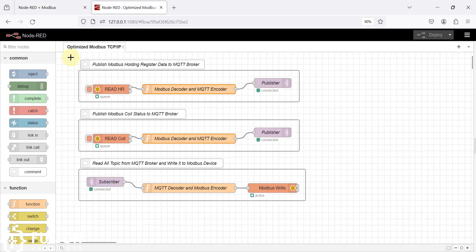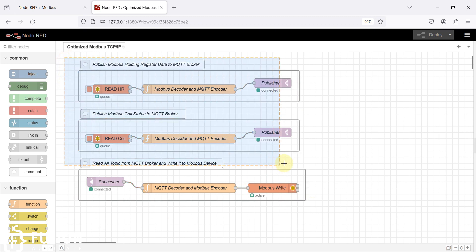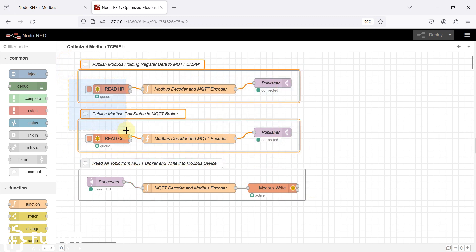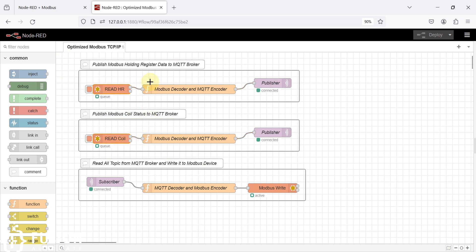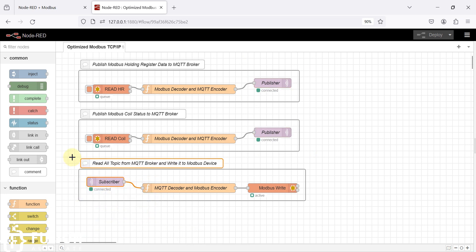Here is our Node-RED flow. In the first two nodes you can see it is reading data from the Modbus TCP device, decoding it, and creating a payload for MQTT, then publishing that payload to the MQTT broker. Whenever any MQTT client writes something on any topic, it will get that topic, decode it, and based on the topic and value it will write that data back to the Modbus device.